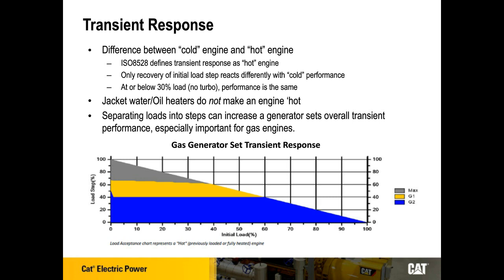You're either in the blue, yellow, or gray, and the difference is: blue represents a G2 class performance of the engine, which is part of ISO 8528. Yellow means it's a G1 class response. Gray means it doesn't meet either G1 or G2, but the engine will still recover from that size load step—it's just going to have a frequency dip outside the range of the classes defined by ISO 8528.